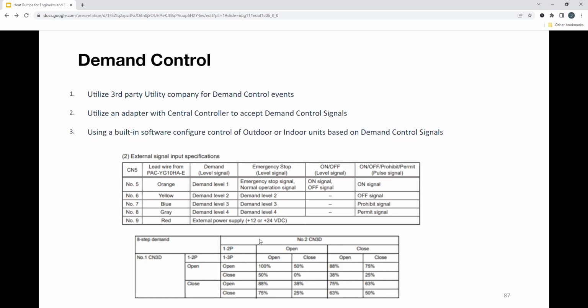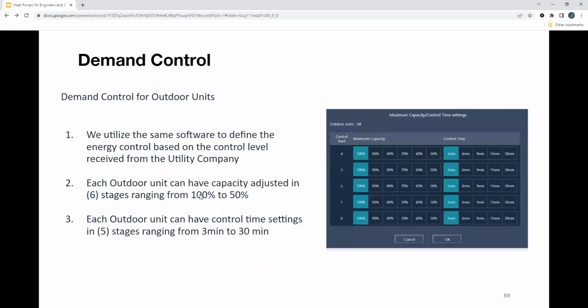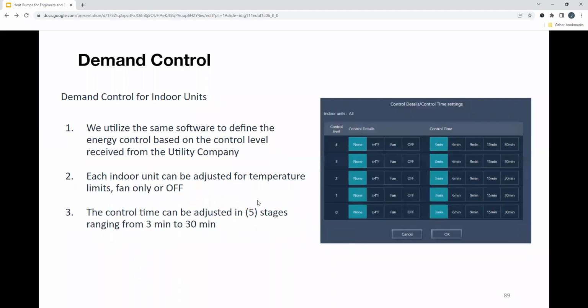Now, the one thing I'll mention is this does save energy, right? But this also does affect the occupants' comfort within that space. If you're reducing certain capacities at certain times, then there's a chance that the temperatures rise or drop and start to fluctuate. So it does get uncomfortable. So you have to choose your priority when you're doing that. Do I need to save energy at this time, or am I worried about my occupants' comfort in the space? So, demand control, same thing. You can limit to percentages and set up your control times for outdoor units and indoor units.